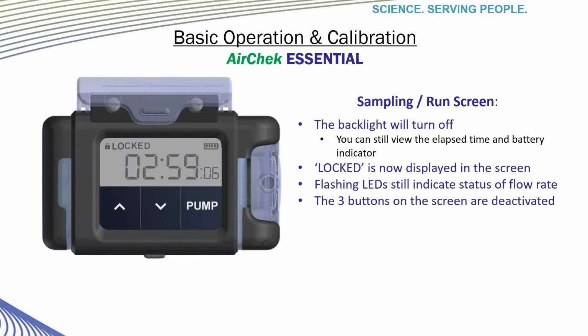The backlight is now off, so the screen will appear dark, but you can still view the elapsed clock, the battery indicator, and whether or not there has been a fault during the run. Locked will appear and stay in the display on the screen, and the flashing LEDs will continue to give you the flow rate status. The three buttons, and this is key, the three buttons on the keypad are now inactive. So even if someone raised the protective cover and tried to press the buttons, nothing would happen because they are inactive.